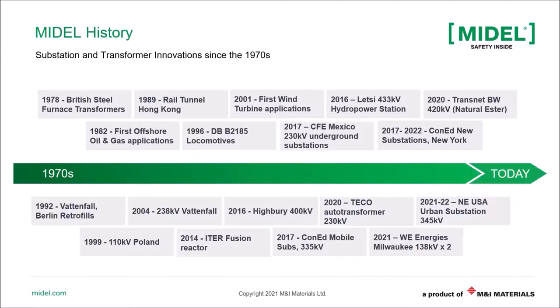Okay, so what you see on the screen here is just a screenshot of what our history looks like. MIDEL esters have been around since the 1970s. The first application in transformers was in 1978. It was used by British Steel to retrofill their furnace transformers. The original use was to remove PCBs out of transformers and replace them with fire safe liquids. That's how we started the use of it. And through the years, MIDEL esters have been used in small distribution transformers all the way up to 2021, where it's used in large power transformers.